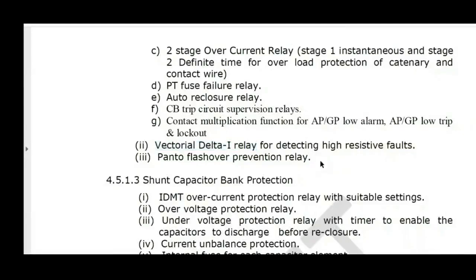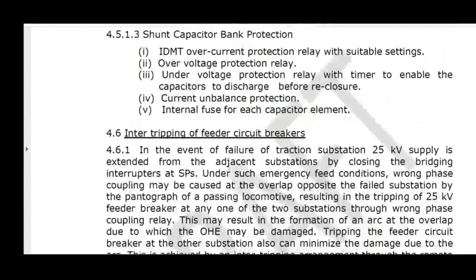Panto flashover we have already seen. So next is the last one, shunt capacitor bank. This is for power factor improvement. And what is the list of protections? It's very simple. You can just see IDMT, we have already seen. Over voltage is also very simple. Whenever the voltage crosses the set value, it's going to be over voltage. If it is below, it's going to be under voltage. Unbalanced protection.